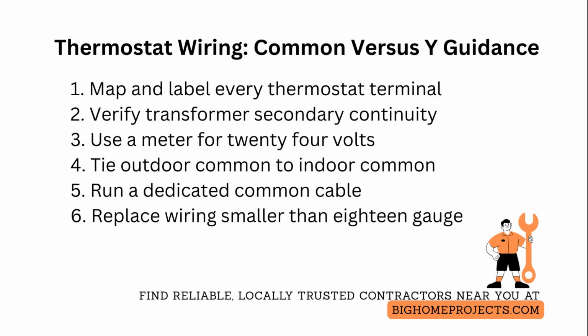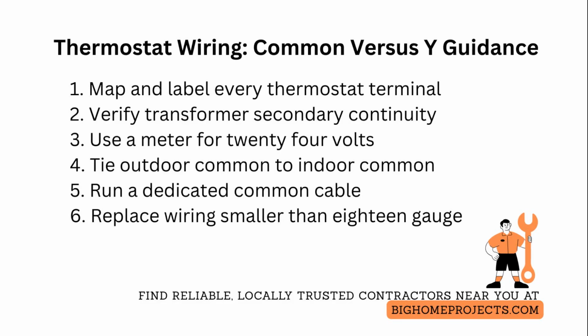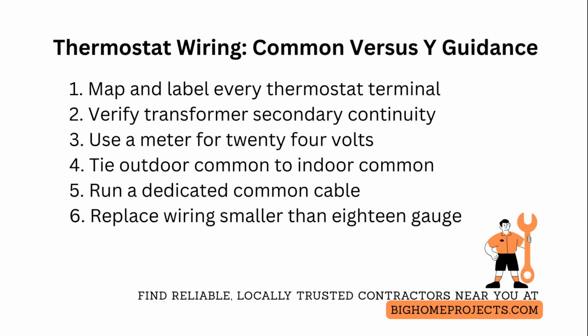If you are replacing a thermostat, map every terminal and label each conductor before disconnecting, then verify transformer secondary continuity between the indoor air handler and outdoor unit. If you see continuity between the two common points, either conductor can be used as the coil return.